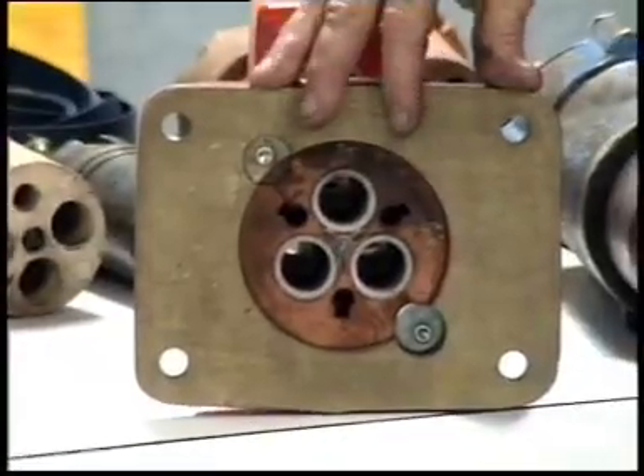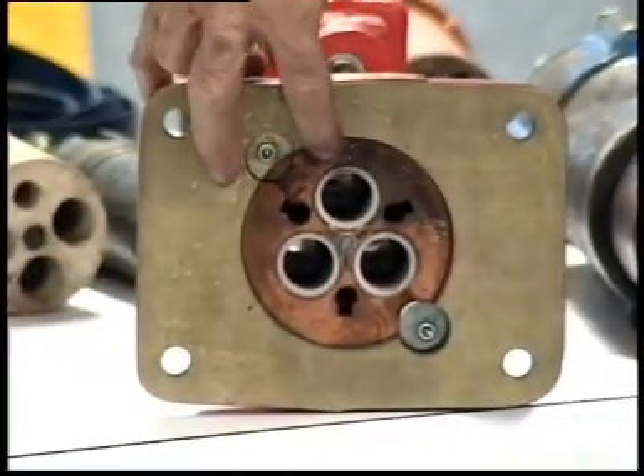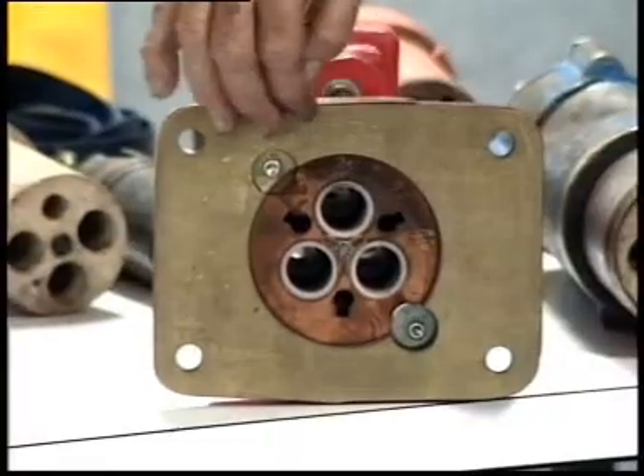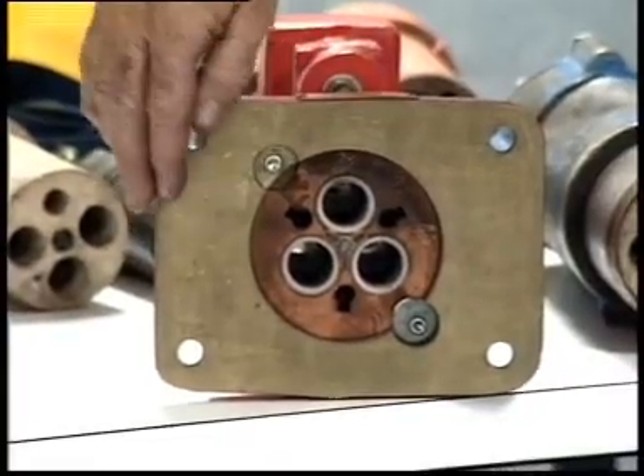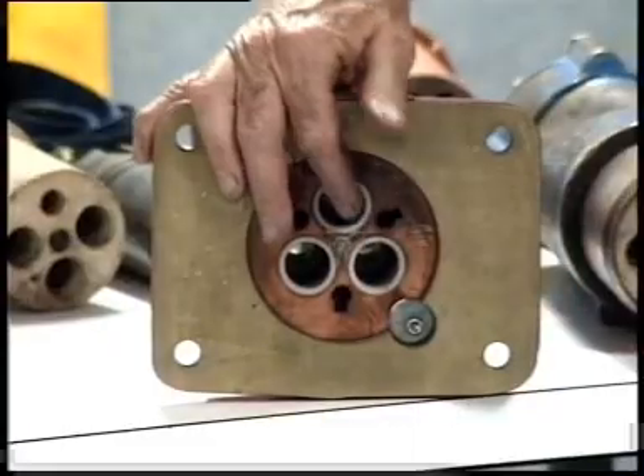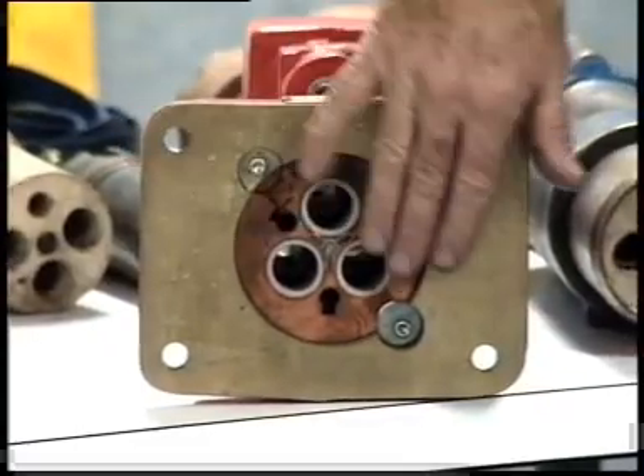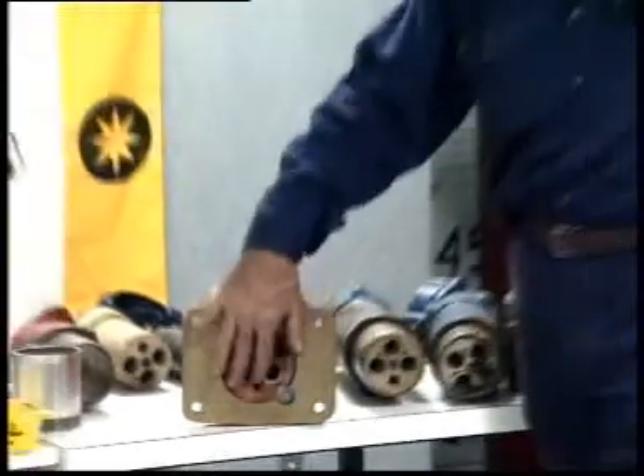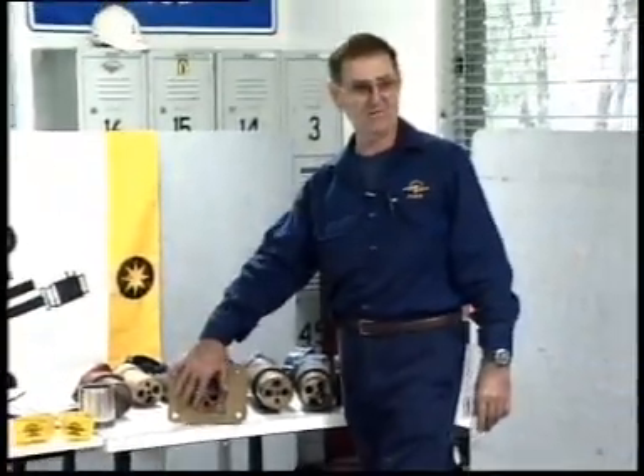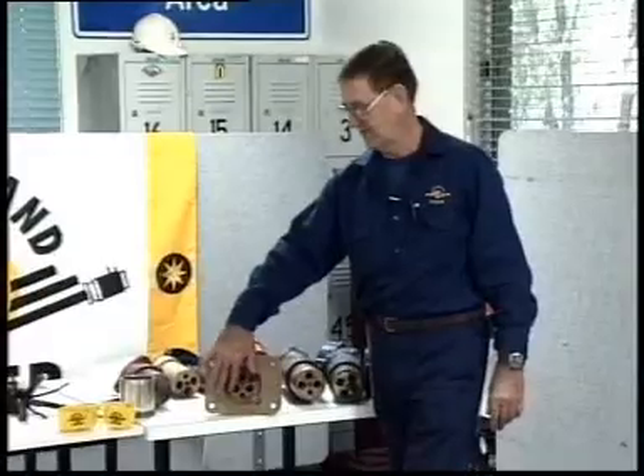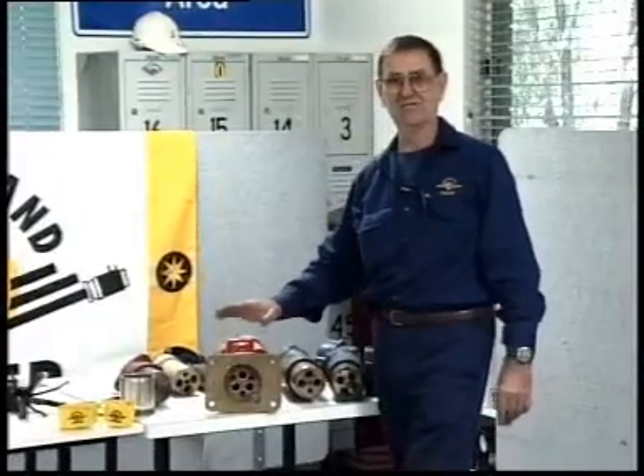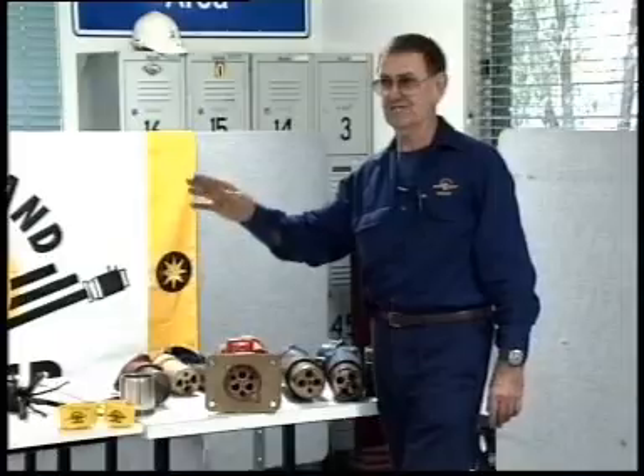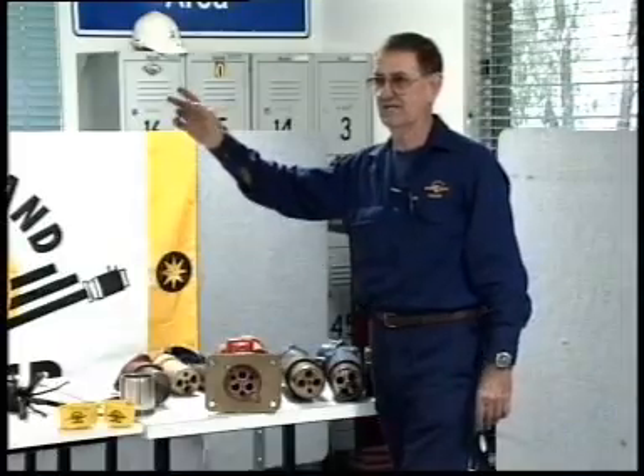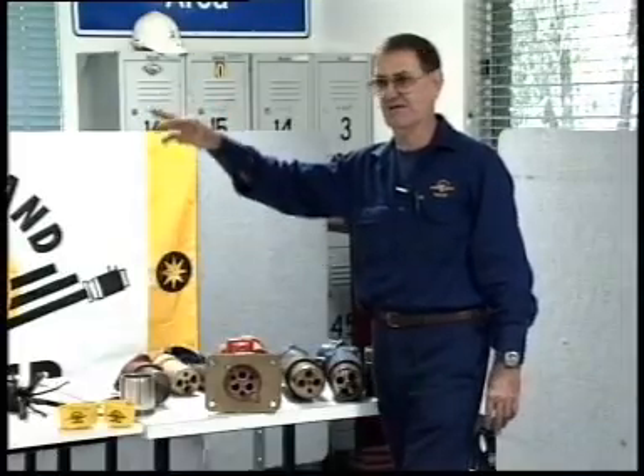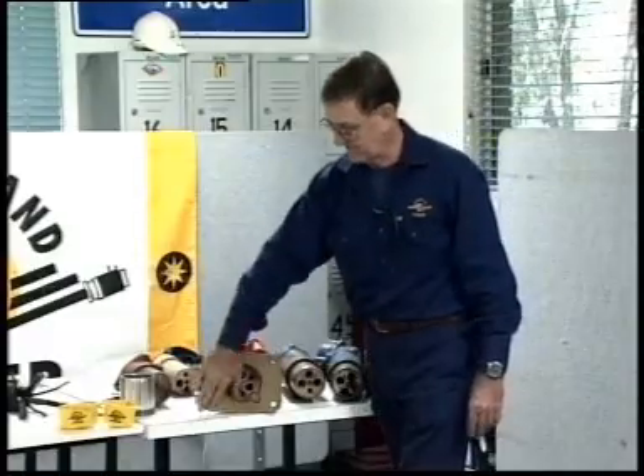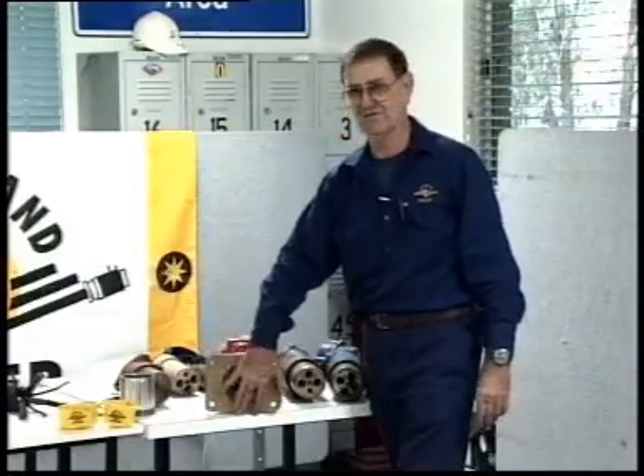What a flame path is, it's a specified gap of a specified length between two mating metal surfaces of a flame-proof piece of electrical equipment. That's what it is. What is it there for? Okay, it's to cool down an escaping flame from an internal fault in the particular piece of equipment it's on. So by the time the flame gets to the outside, it's not hot enough to ignite gas or dust, as we saw before. It's of a less temperature than what we saw methane and coal dust was at. That's the idea of it. So as it passes across these two surfaces where they mate, it cools down sufficiently.